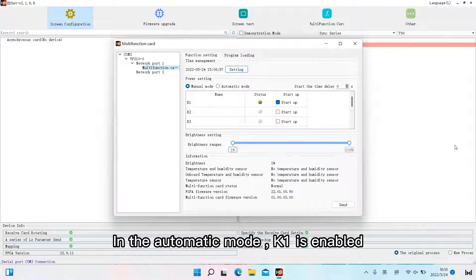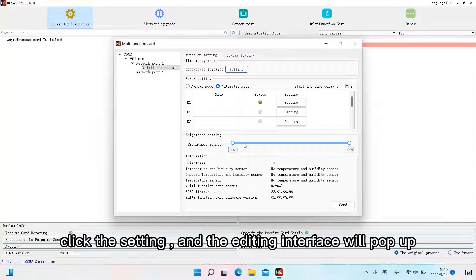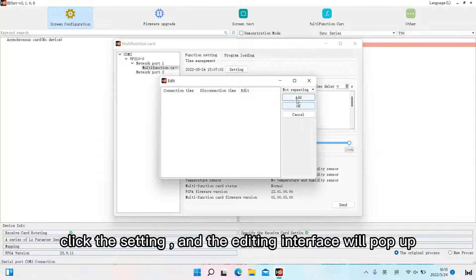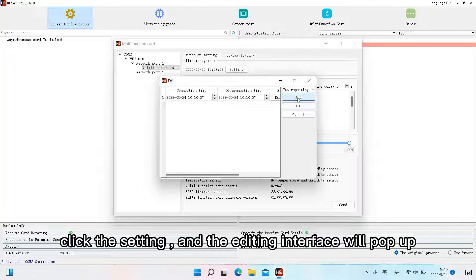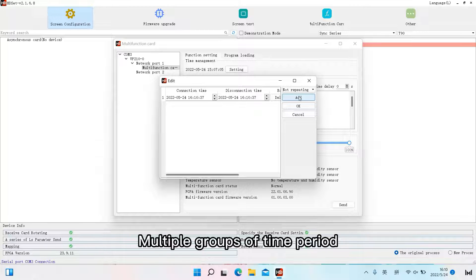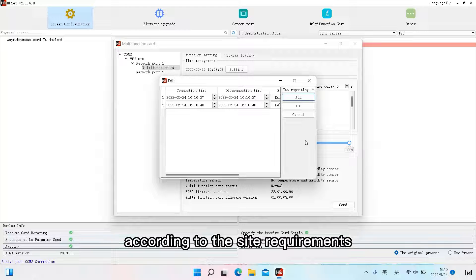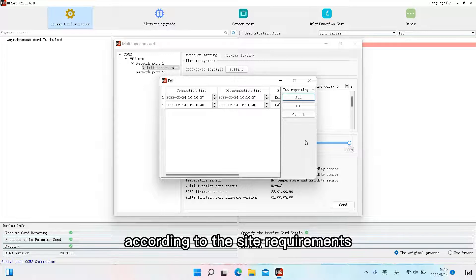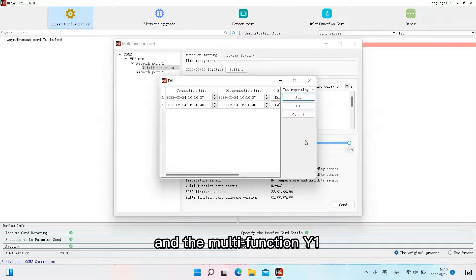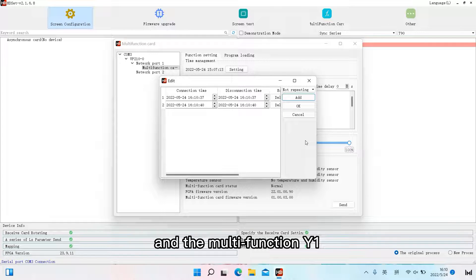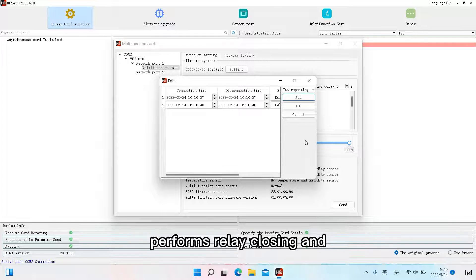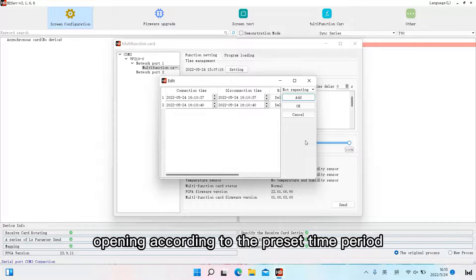In the automatic mode, K1 is enabled. Click the setting and the editing interface will pop up. Multiple groups of time period controls can be added according to the site's requirements, and the multifunction Y1 performs relay closing and opening according to the preset time period.